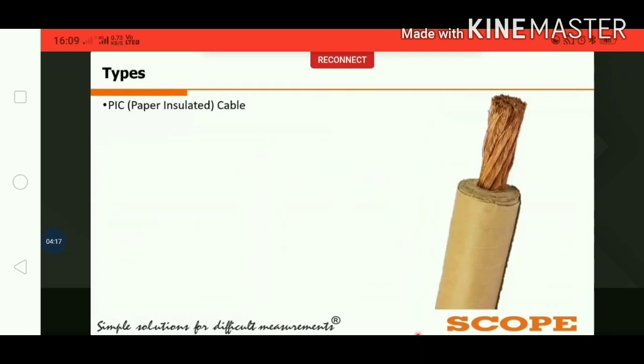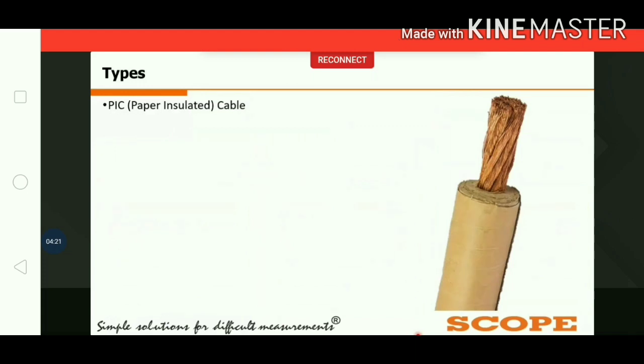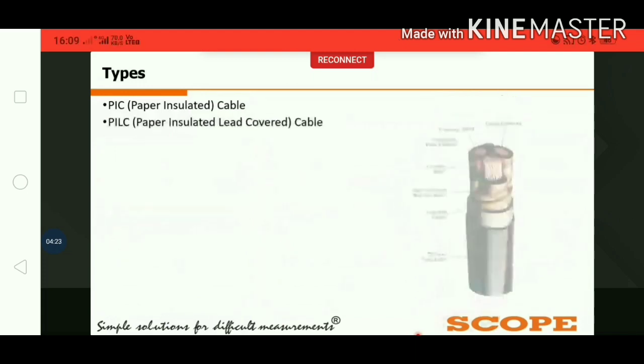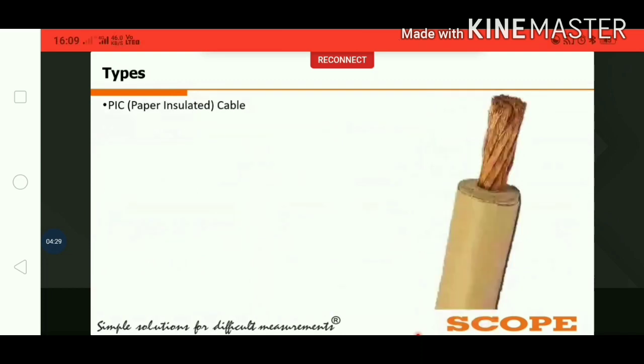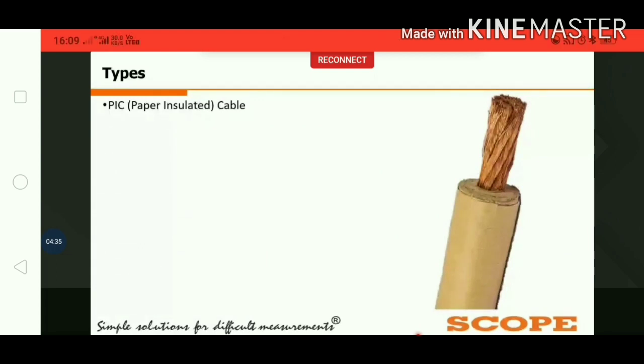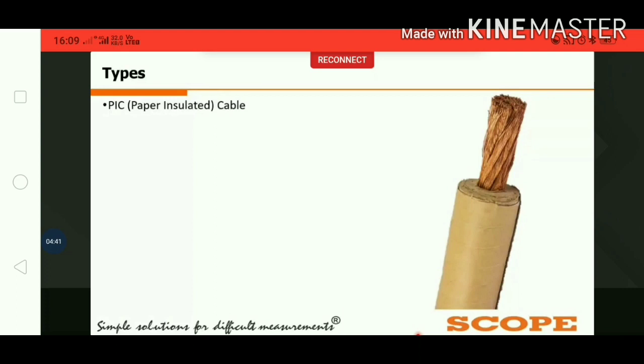First, paper insulated cables were developed, in which paper is used as an impregnated material. These are low cost and provide high dielectric strength, but they are very hygroscopic in nature. That is why they are used for smaller installations like household and LV applications. After that, paper insulated lead cover cables were developed.